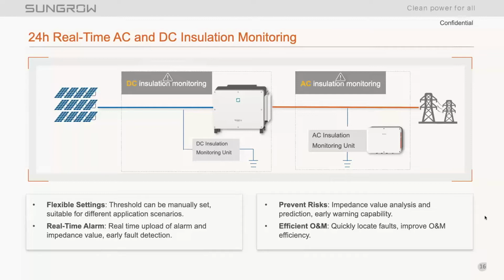We all know the importance of monitoring the DC health, and for years, Sungrow has been kind of an industry leader as far as insulation monitoring goes. We've always employed kind of a 2-tier approach to our DC health monitoring. There's been a residual current detection and insulation resistance monitoring. Insulation resistance monitoring kicks in the morning before the inverter enters its solar duty cycle. And as the inverter is going through its countdown cycle, it's going to measure the insulation resistance to ground. And it's the 350 is still going to do that. That's going to be a staple, obviously because it's required, but because it's kind of a best practice as well.